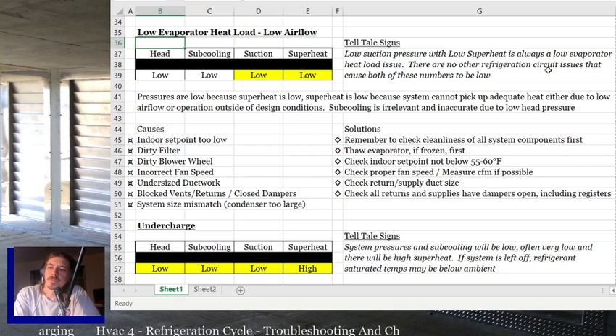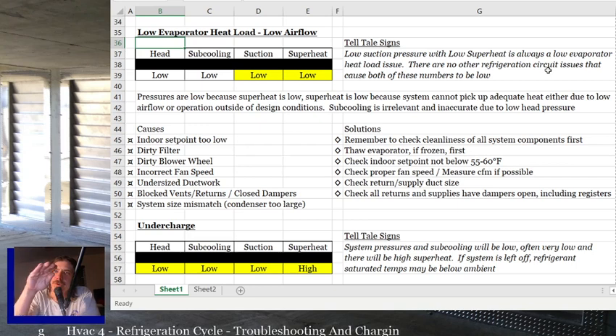One of my favorite examples, and we'll probably talk about it again with duct sizing, is we did a building one time where it was basically, it's a long story, but it's basically a 20-ton outdoor on a 10-ton indoor. When you see that, everything seems like it's working fine for the first hour. And then after 4, 5, 6, 7 hours, you just see that suction pressure and that superheat slowly die, because it just keeps going and going until it finally all freezes up and it isn't working. So just slightly low airflow, 325 CFM per ton, can throw you in that vicious cycle sometimes.